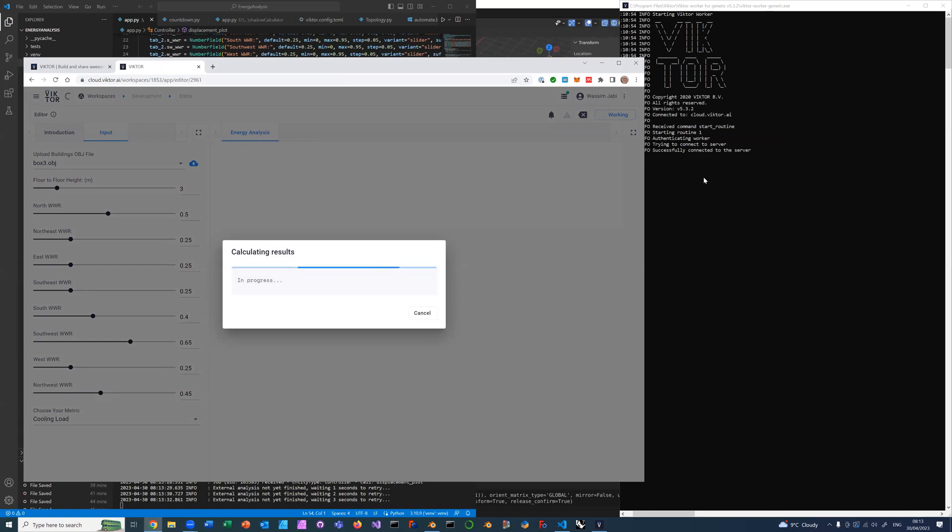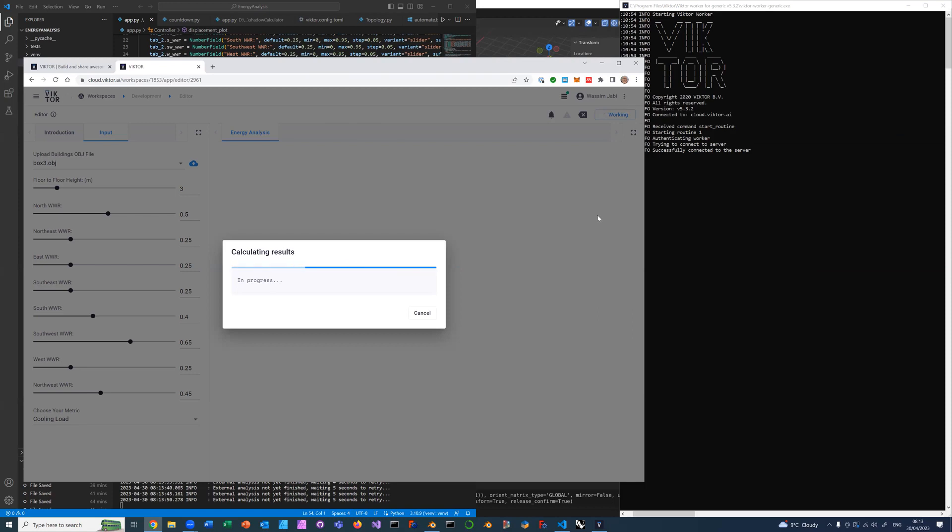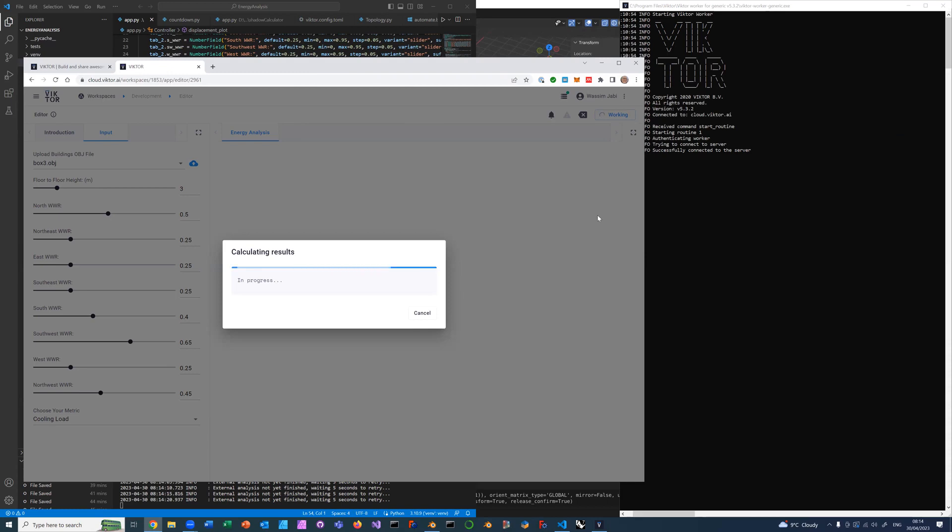This will take a few minutes to do the simulation. It's now running OpenStudio and EnergyPlus in the background on my server, which happens to also be my laptop, but this could have been a third-party server somewhere that has all this running on it. It will take the building and slice it horizontally based on the floor-to-floor height. It will look at the exterior walls, inclined and vertical. It will find their compass angle and apply the correct window-to-wall ratio.